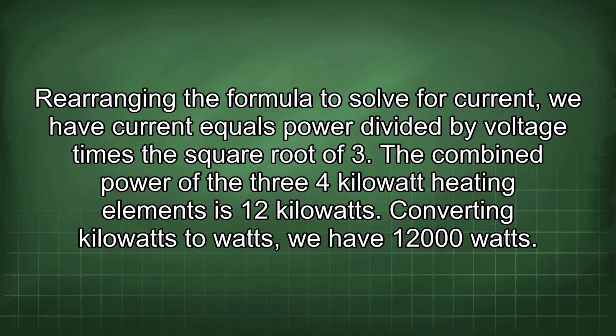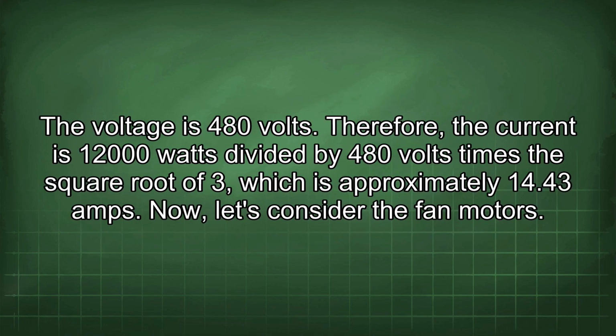Rearranging the formula to solve for current, we have current equals power divided by voltage times the square root of 3. The combined power of the 3 4-kilowatt heating elements is 12 kilowatts. Converting kilowatts to watts, we have 12,000 watts. The voltage is 480 volts. Therefore, the current is 12,000 watts divided by 480 volts times the square root of 3, which is approximately 14.43 amps. Now, let's consider the fan motors.